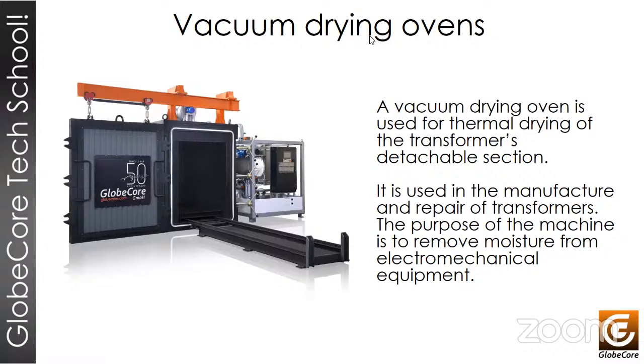Due to its capillary structure, paper insulation is highly hygroscopic. Transformer oil is somewhat less hygroscopic. Therefore, after outdoor exposure, the active section becomes humid, even as it is impregnated with oil. Moreover, in old transformers without air dryers, the insulation becomes humid during long-term operation. If windings are made again, their insulation also features an increased humidity.